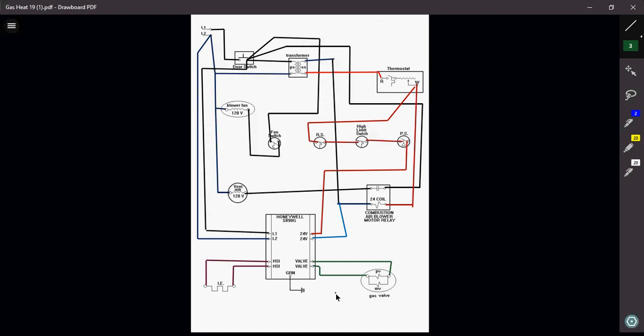satisfies. And once the thermostat satisfies, the vent motor will shut down because the coil on my relay here will de-energize, which will open those contacts, de-energizing my motor. Once that motor starts to slow down and stop, my pressure switch opens, and it kills the 24-volt signal down to my ignition module, which virtually shuts everything down. So, that's how you wire a hot surface ignition system.